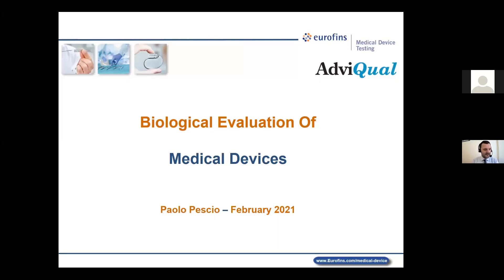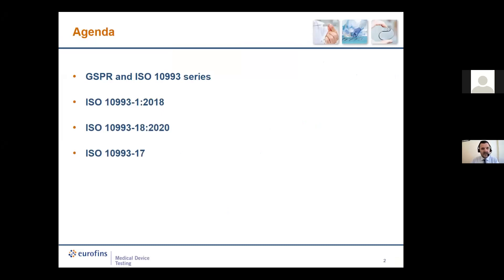Today we'll evaluate a medical device from another perspective, starting with the MDR and the general safety and performance requirements. We'll briefly cover how the ISO 10993 series fits the purpose, then look at ISO 10993-1 of 2018 and the main changes in our approach to biological evaluation. The most relevant change is the request for chemical and physical information as a prerequisite. We'll also look at the brand new ISO 10993-18 of 2020 and a flavor of the toxicological risk assessment covered by ISO 10993-17.